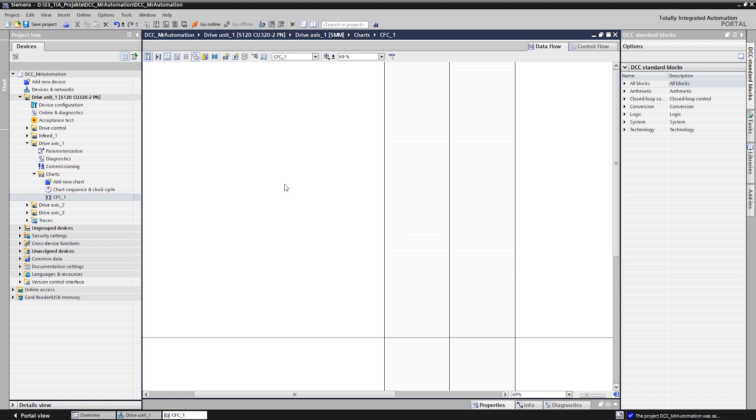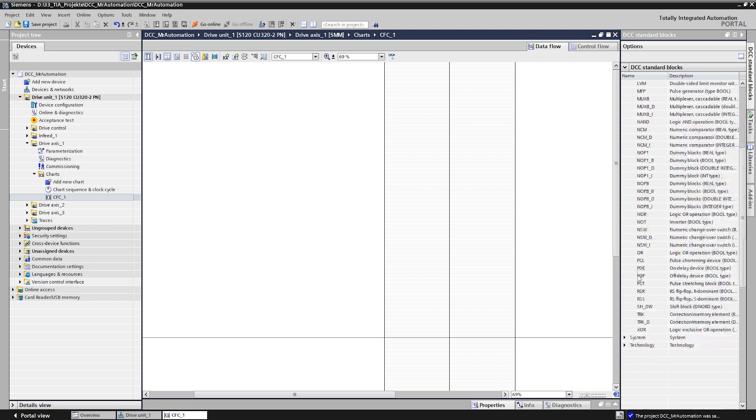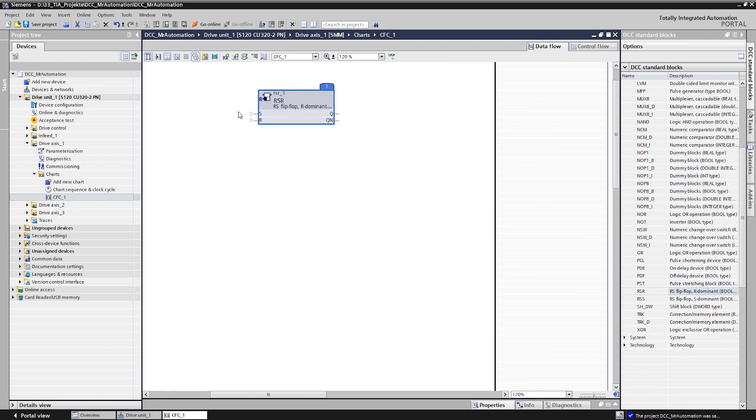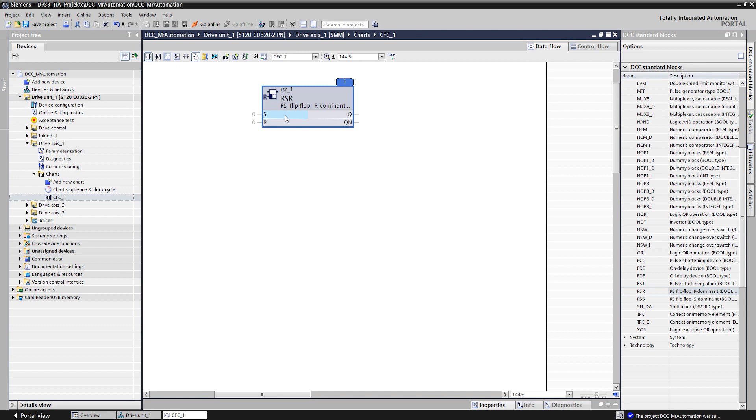Since we want to switch on the drive with only one push button, we need a set and reset flip-flop. This can be found in the logic entry and we drag and drop it to the desired position in the chart. Each block has inputs and outputs, through which several blocks can be interconnected.